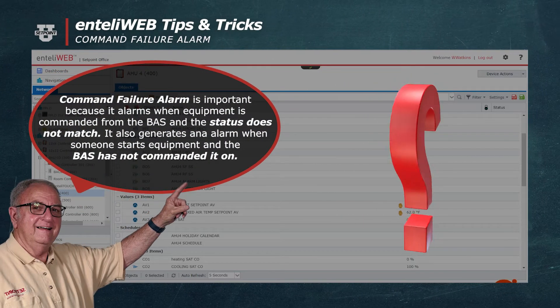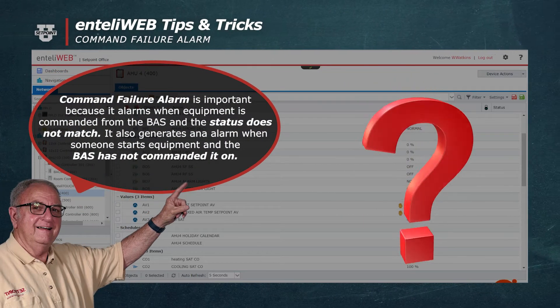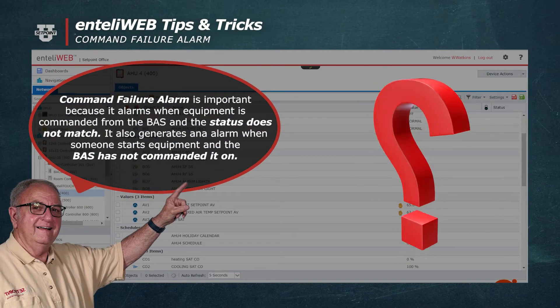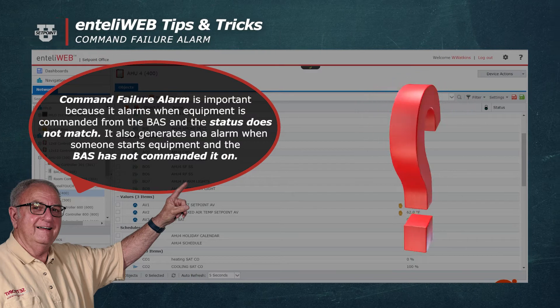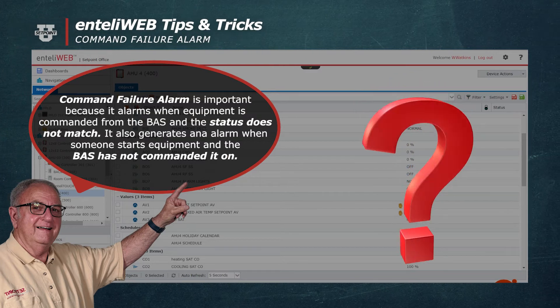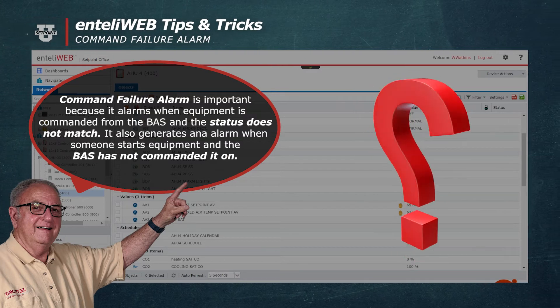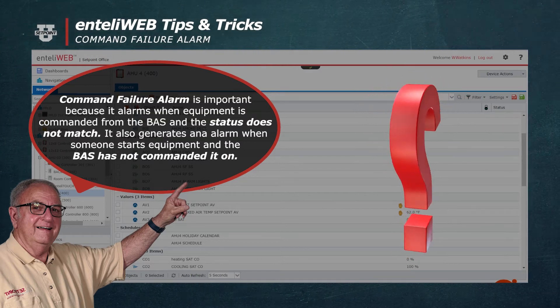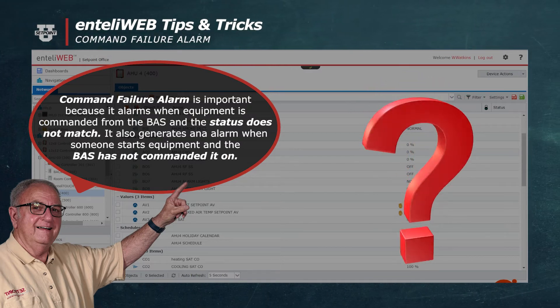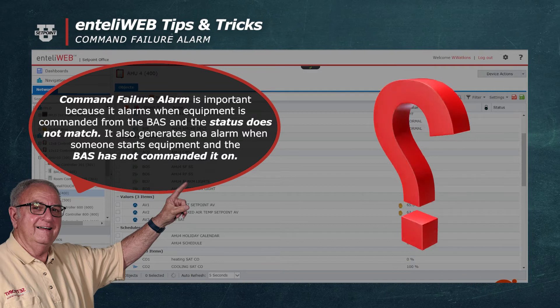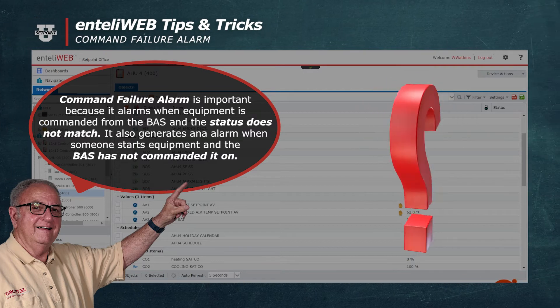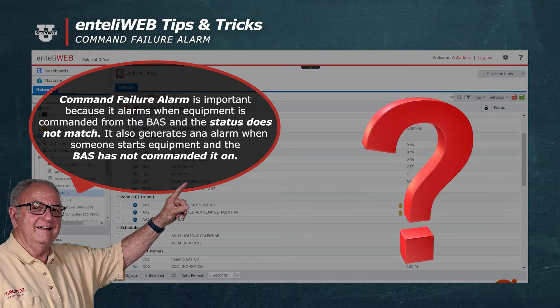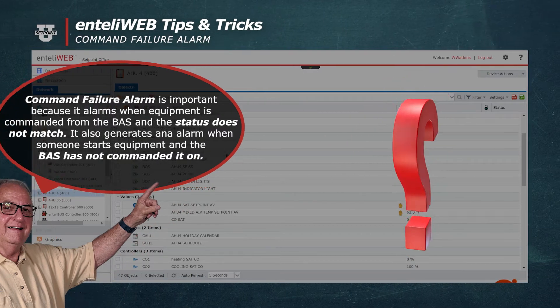Command failure alarm is important because it alarms when the equipment is commanded from the building automation system and the status does not match. It also generates an alarm when someone starts the equipment and the BAS has not commanded it on.